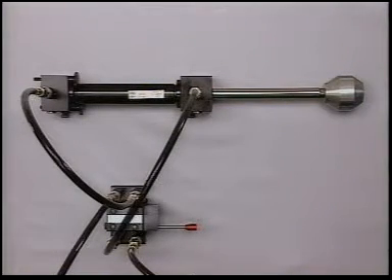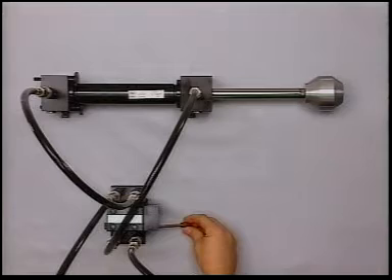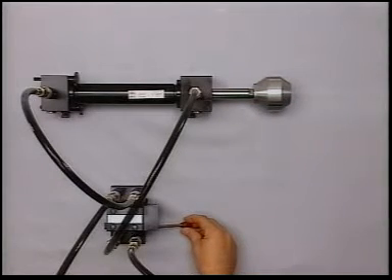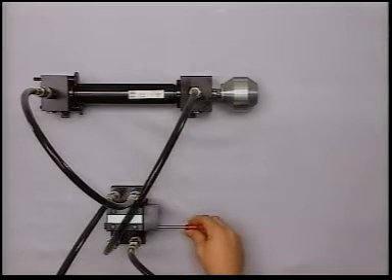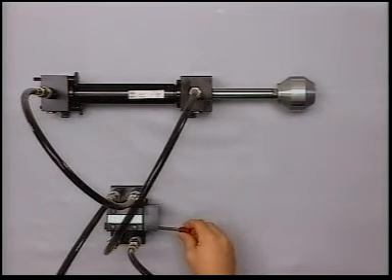This is a differential circuit with a 4-3-way valve and mid-position bypass. In this switching position, the piston retracts rapidly. The first phase of advance is also rapid, because this is where the differential circuit takes effect.